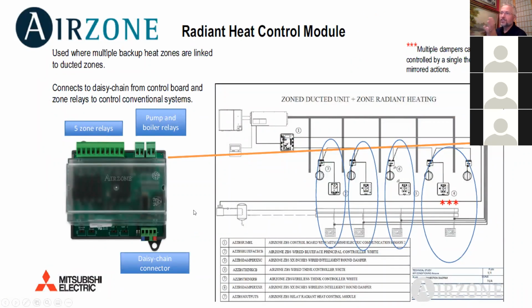So this is sort of the key component for integrated controls as it works with AirZone, this 5-relay module. So this connects to the daisy chain, and then it has a whole series of relays. It's in pairs. So the first two ports are relay 1, zone 1, second pair zone 2, zone 3, zone 4, zone 5. And there's a dip switch in here that if you switch it up, it turns this into zone 6, zone 7, zone 8, zone 9, zone 10.